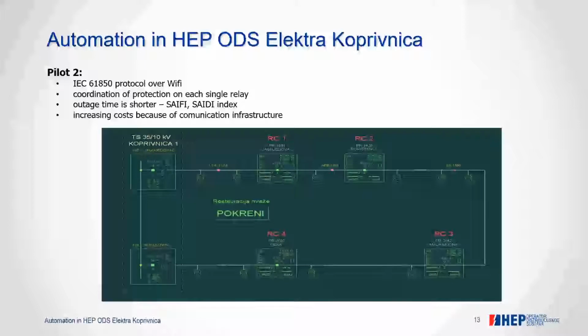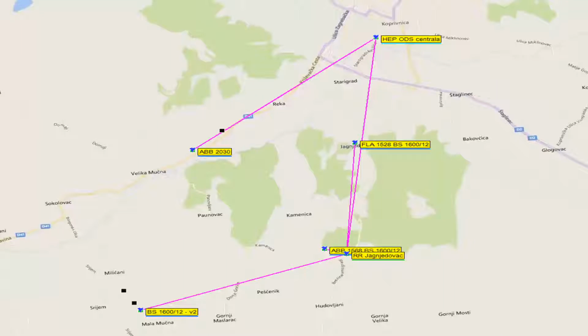So here's the schema on the SCADA system. That's the 4 reclosers. So now we have a shorter outage time, and that helps improve our SAIFI and SAIDI indexes. But we have increased cost because of the communication infrastructure. Here's the schema of the communication infrastructure, and here in the middle are hills with forests. So the left recloser can't see the 3 others. That recloser must communicate with the point upstairs and then down. That's our challenge, and that's a challenge that we managed to solve.